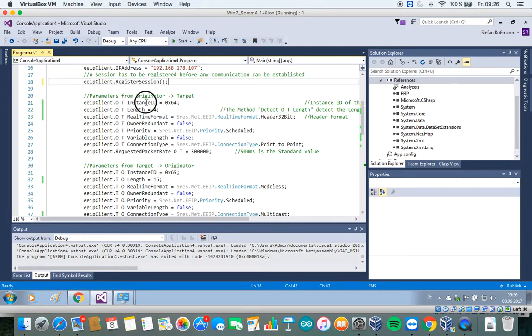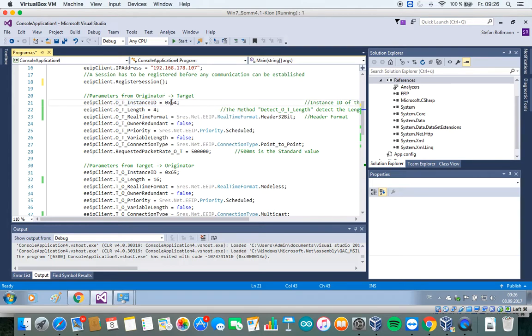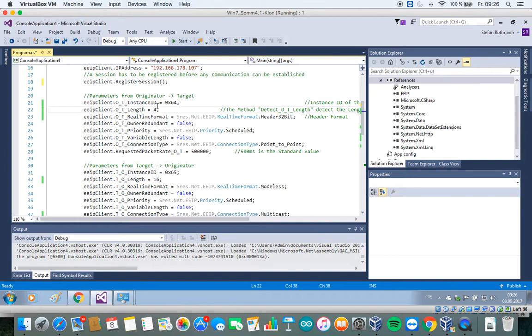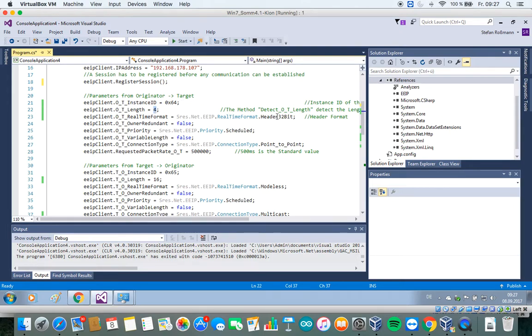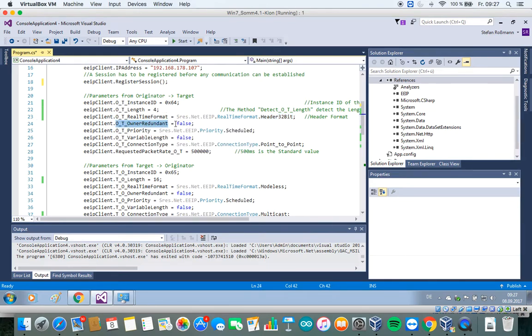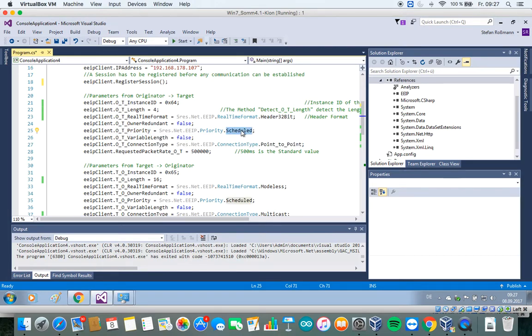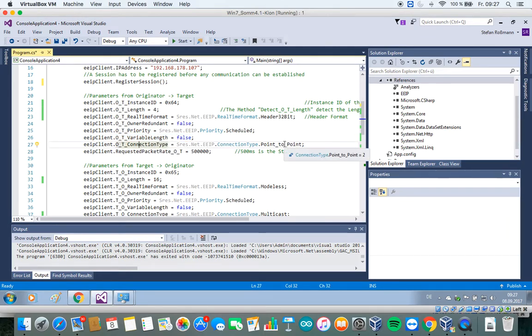So we have to define the instance ID, where we can find the output assembly. So this is 0x64 hex. The length of the output assembly depends on how many modules we attach to our device. In this case, I attached four digital output devices. The header size, owner-redundance, the priority is scheduled, variable length is not supported by this device, connection type point-to-point.